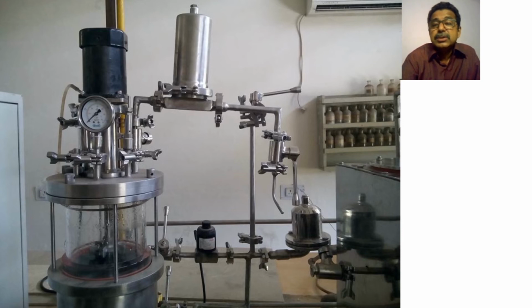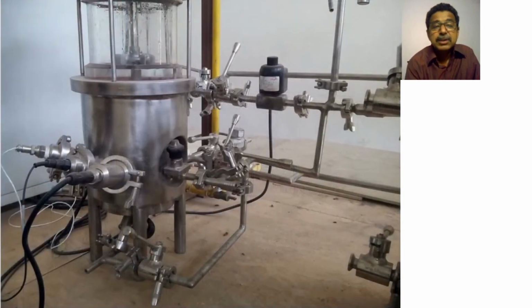Normally we use a Teflon disposable filter, which many times is also sterilizable. So for some runs we can sterilize and reuse it. By and large these air filters are present, with porosity of around 0.2 to 0.4 micron.